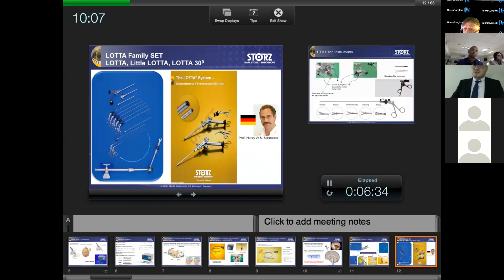Why 6? Because as soon as the instrument tip comes out from the working channel, the surgeon wants to see it, not have it go a little bit far before they see the tip, as with the 0 degree. With the 6, you see it as soon as the head comes up, and you can see the instrument easily. The LOTTA is also available in 30 degree, especially to see the aqueduct. So it is available in both, but the 6 degree is the mostly used telescope.